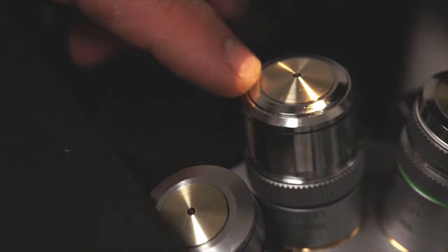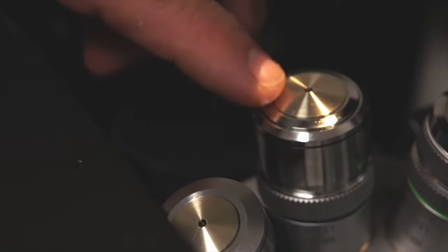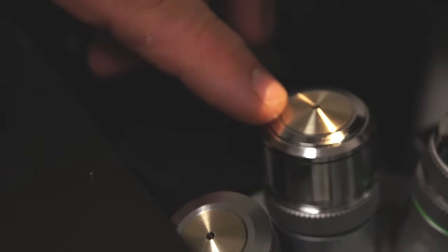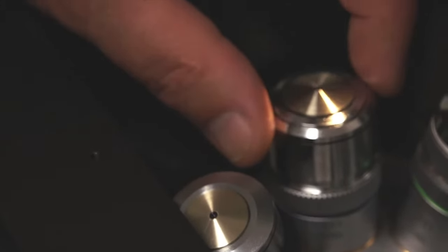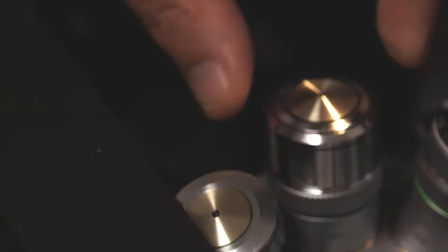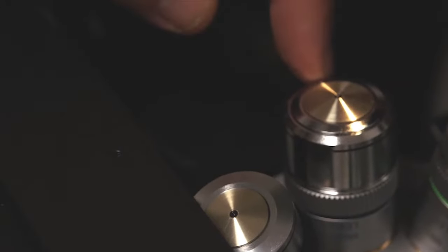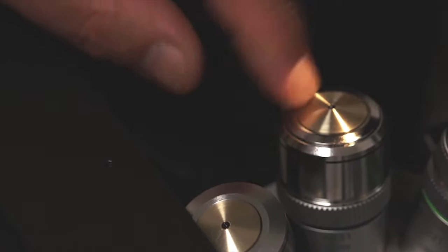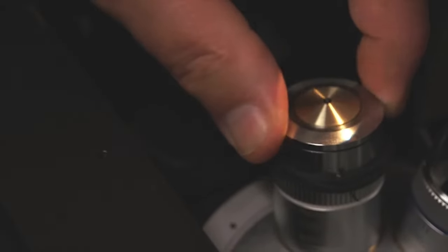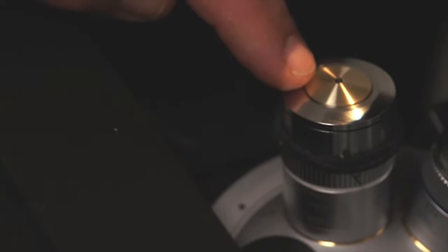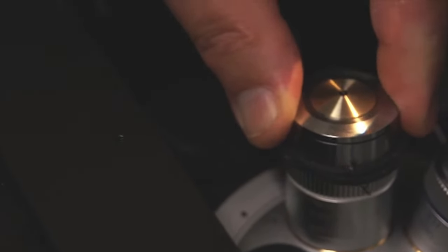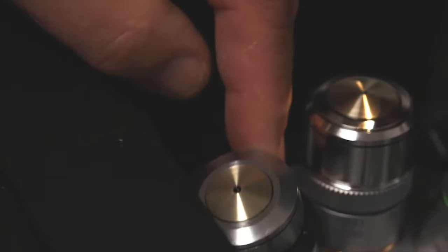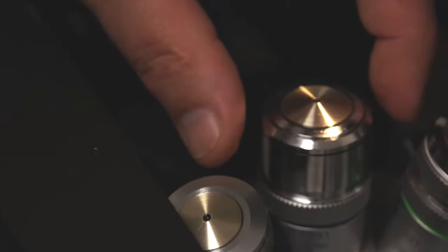Because the 63x objective and the 100x objective are very expensive objectives, they have a unique feature that allows you to lock the front element down and out of the way so that when you're rotating the nose piece, these objectives will not come in contact with the slide. The 63x objective does that, and also the 100x objective locks down and out of the way. Please keep that in mind, as a previous user may have locked it down and out of the way, so that in order for you to do your work, you have to unlock the objective and let it come back to its full height in order for it to work properly.